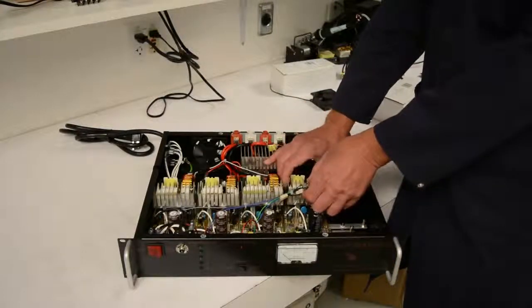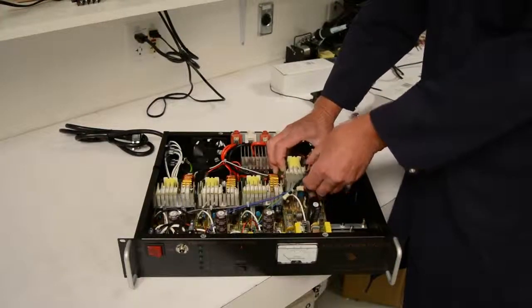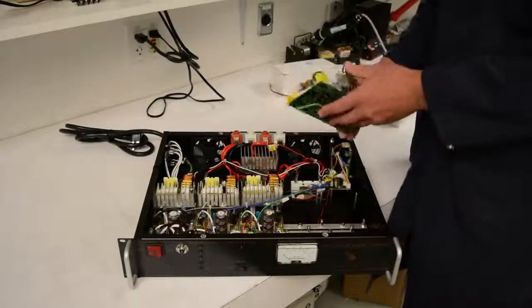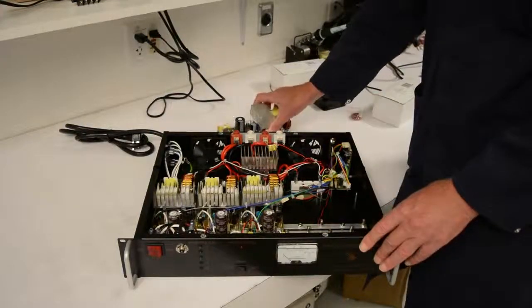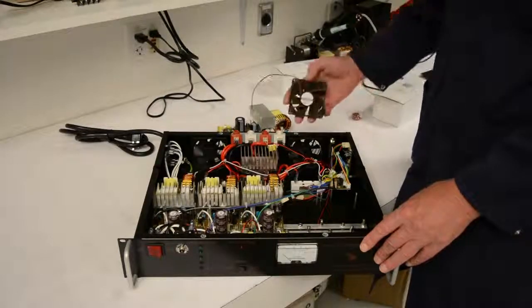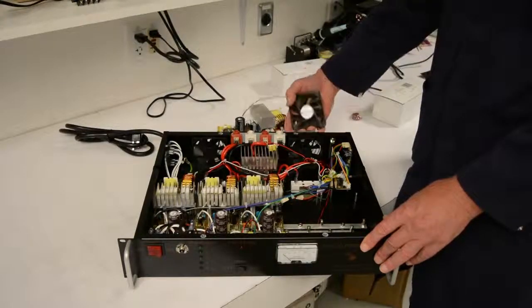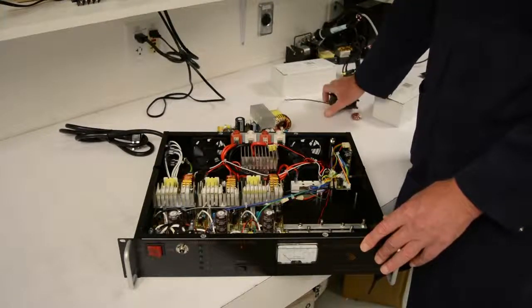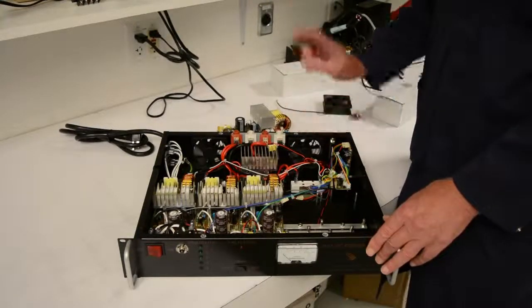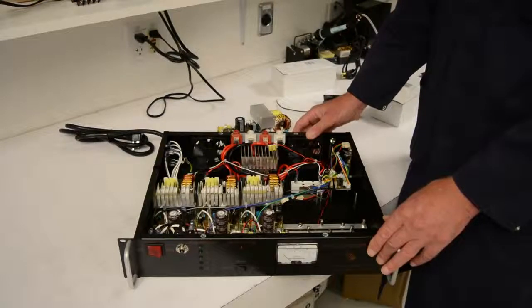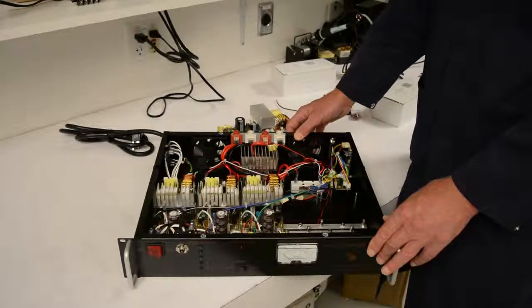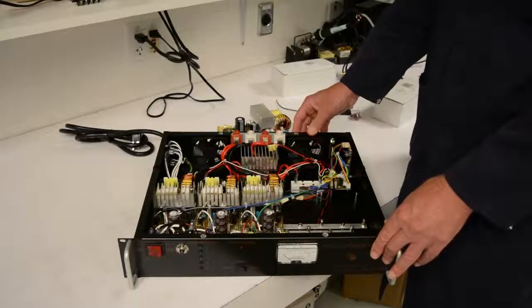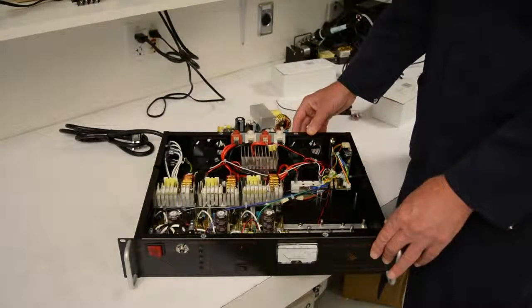It's a very good indicator of how easily it is to upgrade or how easy it is to repair the unit itself. The fans themselves, they're easily replaceable. Four screws in the back and the fan pops out and you replace the fans. It's best to replace two of them at the same time, because if one of them is going, then the other one's probably going to be gone very soon anyway. So they're relatively inexpensive and easy to replace in the field.